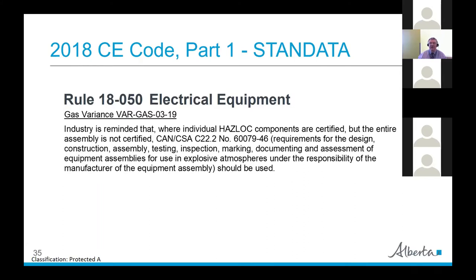Another STANDATA on hazardous locations reminds industry that while individual hazardous location components are certified, the entire assembly may not be certified. There is a standard — CSA 60079-46, a Part 2 standard for equipment — that should be used to make sure that the installation and equipment is safe.